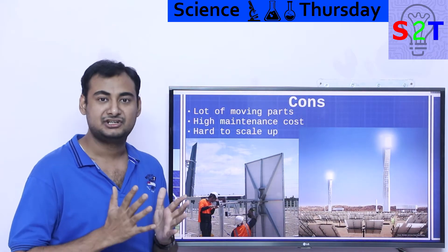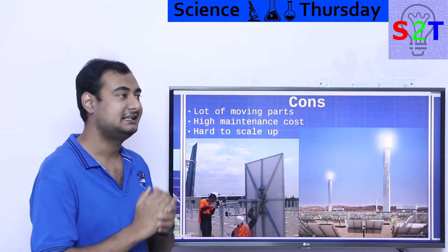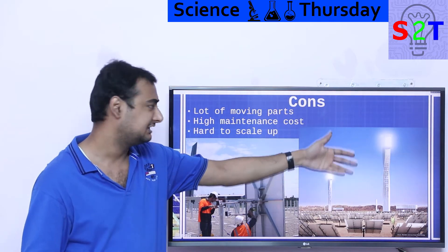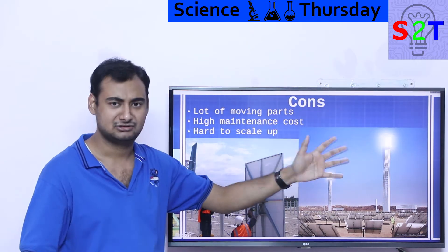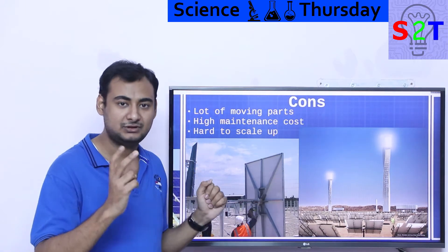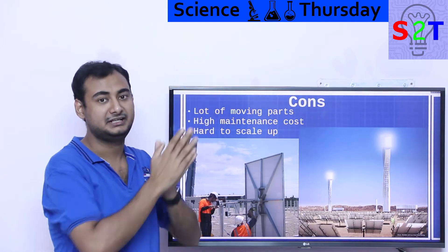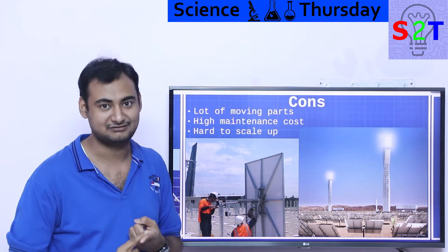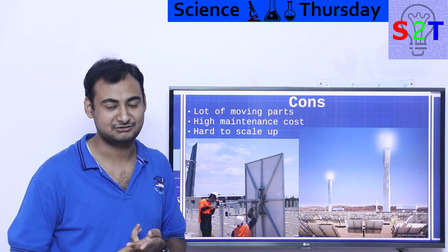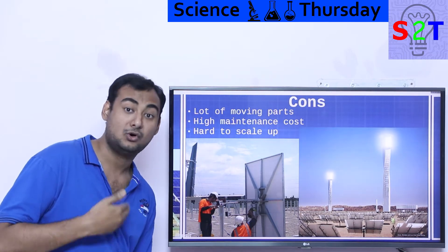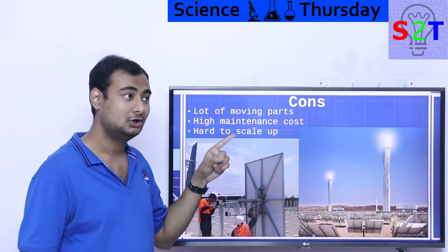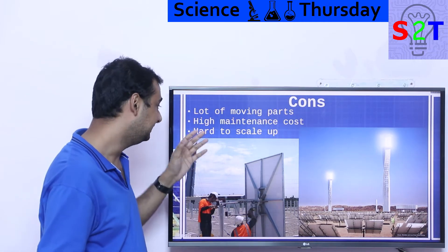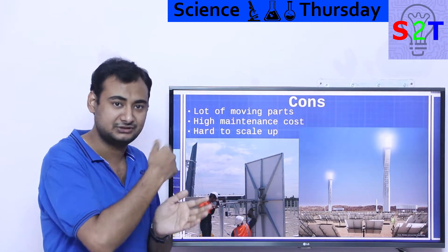But what are the cons? Engineering's first principle: complexity is the enemy of reliability. Solar thermal has lots of moving parts. Each of these mirrors has a two-axis tracking system. How many mirrors are there? Thousands. That means thousands of bearings, thousands of motors, thousands of motor controllers to manage. That inherently means very high maintenance costs. A photovoltaic solar farm you put it and forget it. This system requires like a whole small army to keep maintaining — it's not something you put and forget.